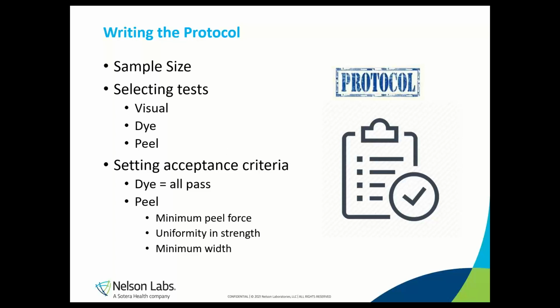The first step is to write the validation protocol, where we document the test plan, or what we're doing, why we're doing it, and what we're expecting the outcome to be, or our acceptance criteria. We need to know what the sealer capabilities are, what variables can be changed, and what equipment requirements there are so we can incorporate them into our protocol. The purpose of a sealer qualification is to ensure that all seals made on the sealer are continuous, without gaps, and are sufficiently strong for the intended use.